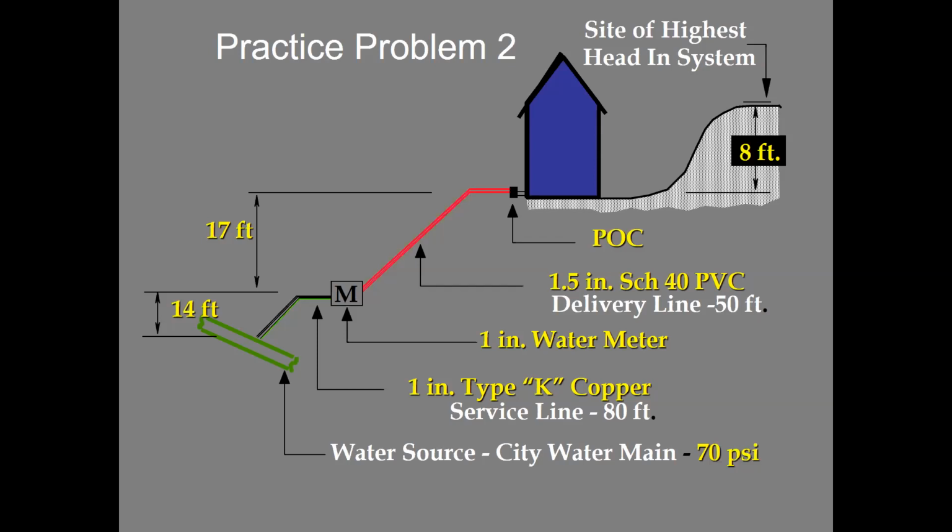Oh, it's just that. Okay, so 79. 56.58. Perfect. So what Dylan did is he took our 70, which is our source at our main, and subtracted that elevation difference, pressure loss. So you take 70 minus the 13.42 PSI loss due to the gain in elevation, and we would have a base static pressure of 56.58 PSI.